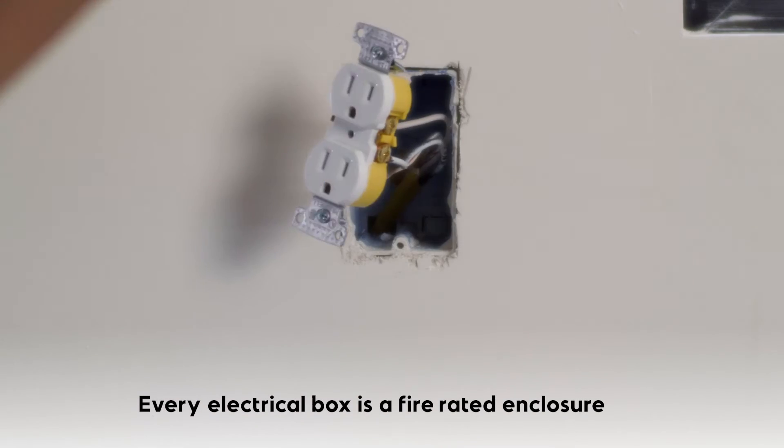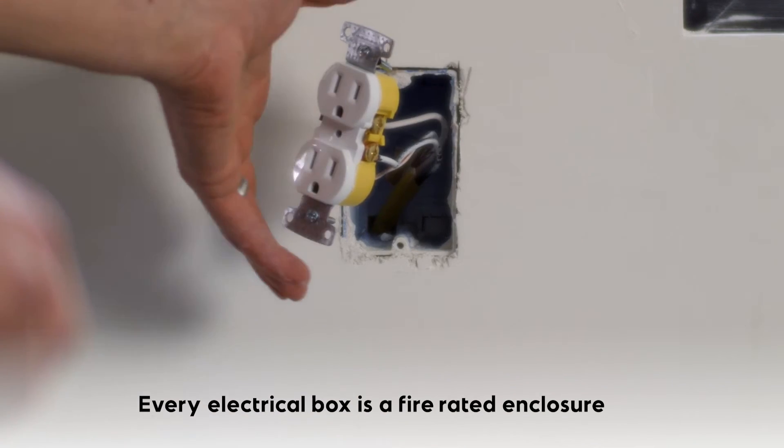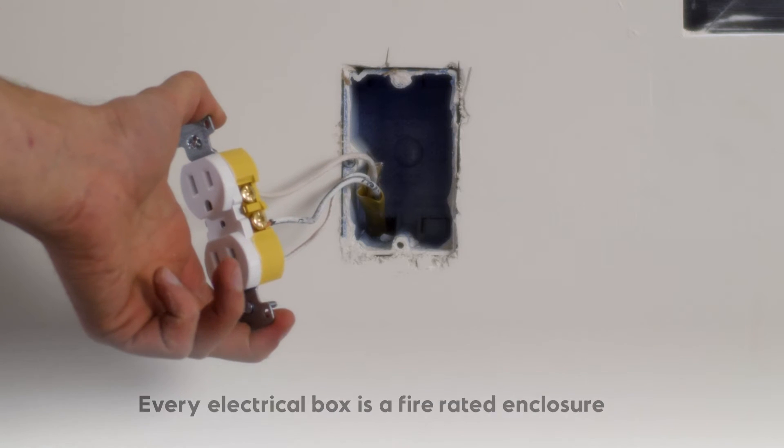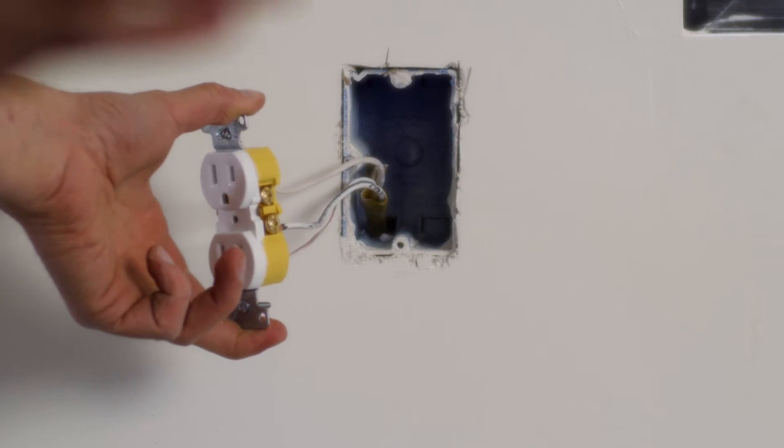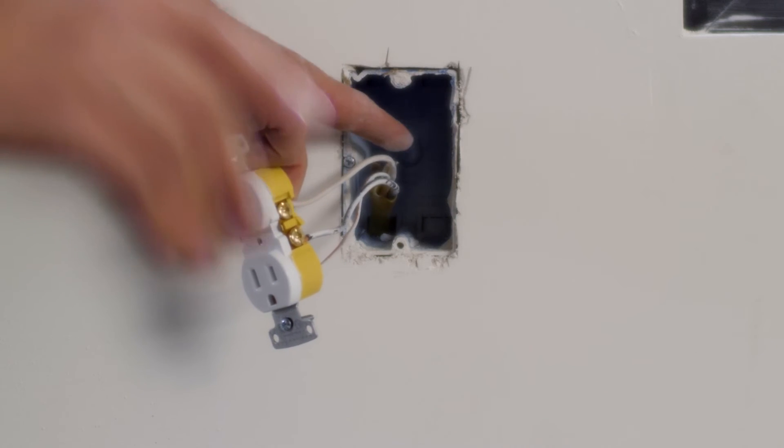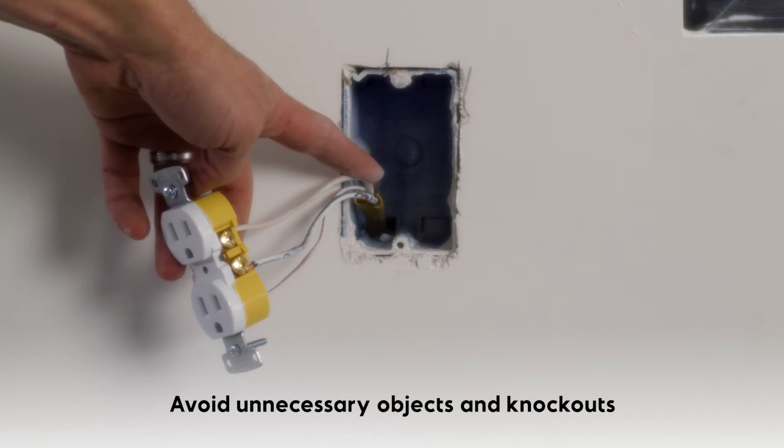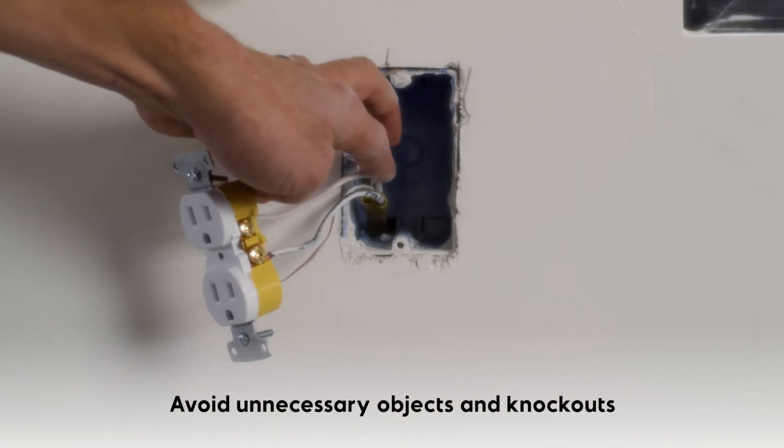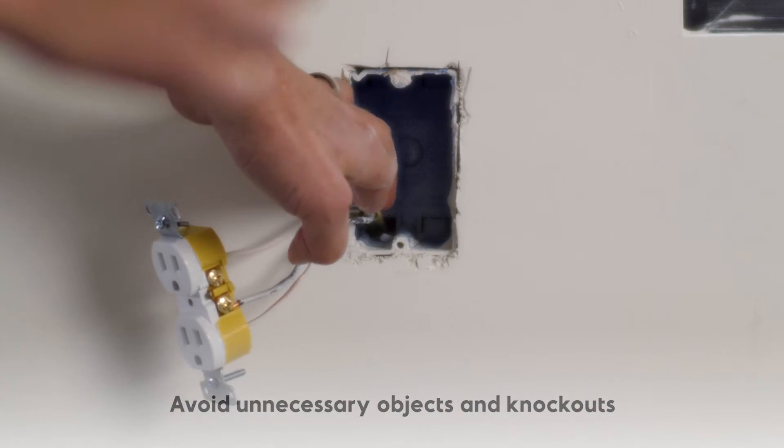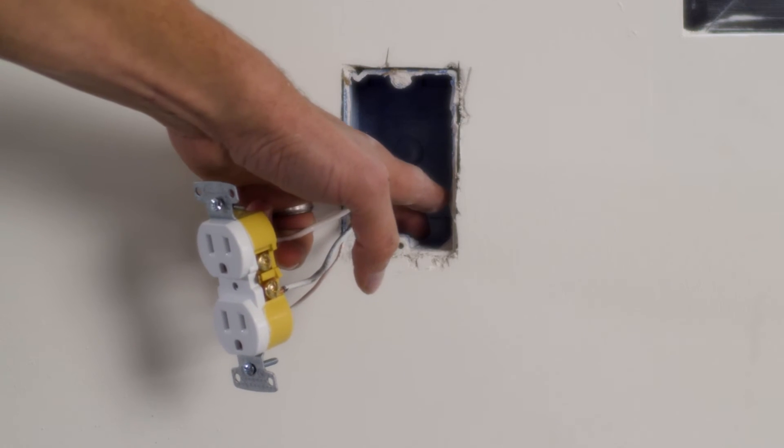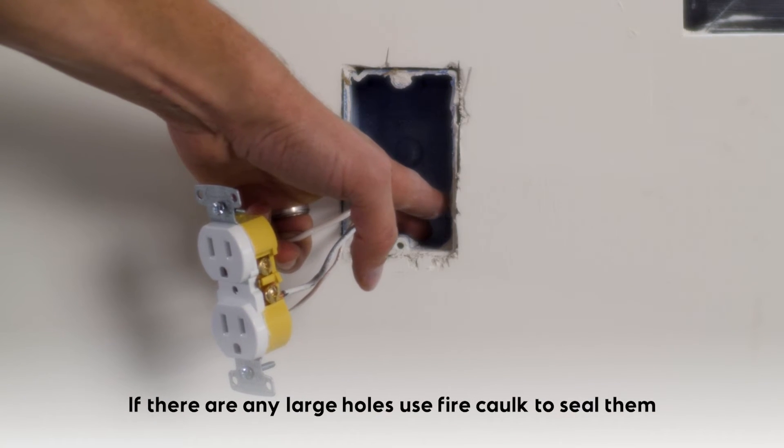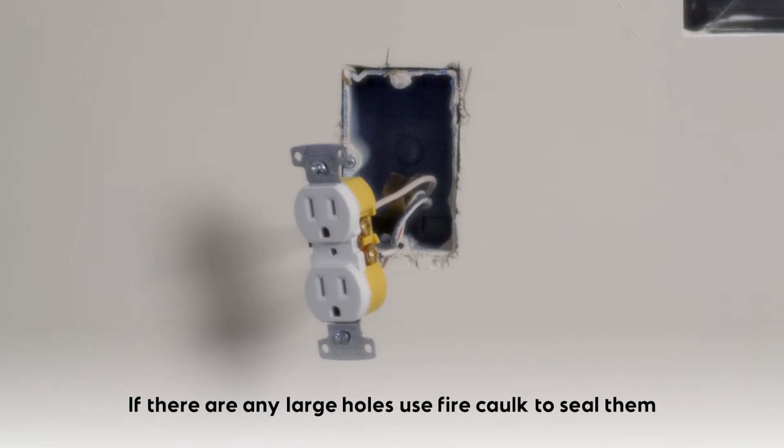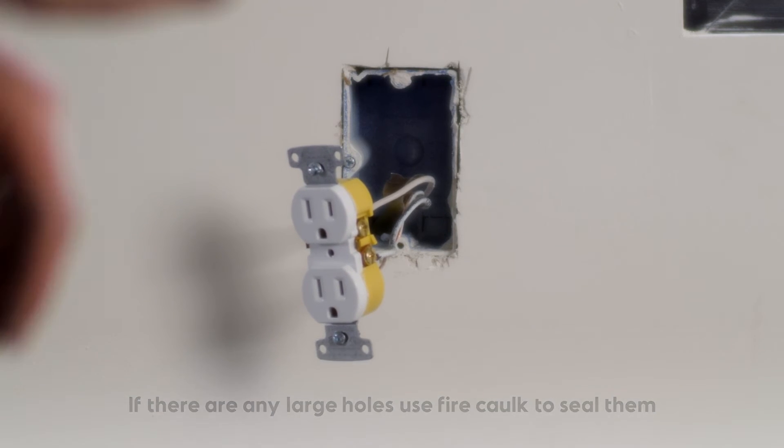Drywall is non-combustible, but I don't really want to have an excessive amount of drywall inside my box. Every electrical box is a fire-rated enclosure, so I want to avoid a couple of things: I want to avoid having wood chips or anything that's combustible. I want to avoid having any type of foreign object. I want to avoid unnecessary knockouts and openings in my box. The box should not be drilled or cut abnormally. If there is a large opening that does not have a wire through it, then I'm going to use fire caulk to seal that hole as part of retaining the fire enclosure of that box.